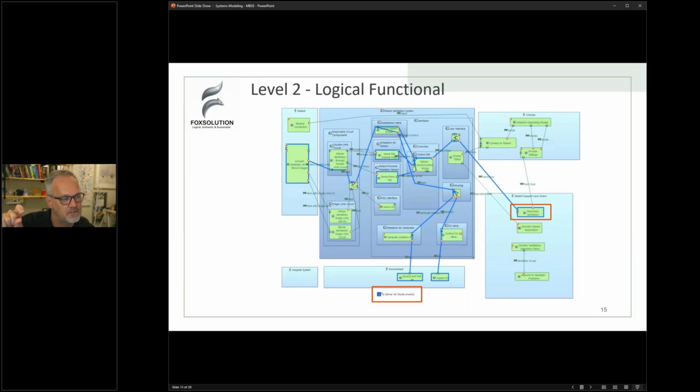Once we understand the function that they're providing, this interface line to the user interface is the thing that we're going to be evaluating in a usability FMEA. Under what conditions do we have a perception and a cognition error that leads to actions that are inappropriate for this specific function that the user is supposed to be delivering to the user interface? That's the axis by which we would do that analysis.